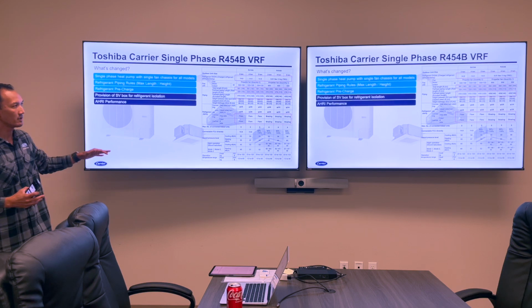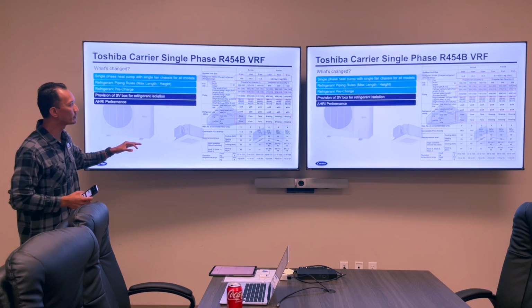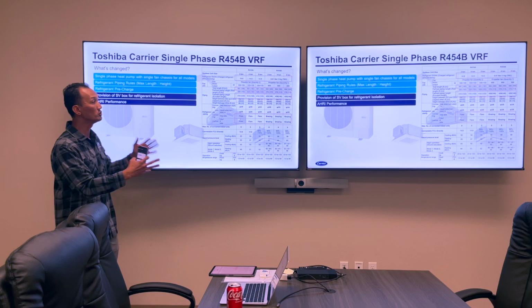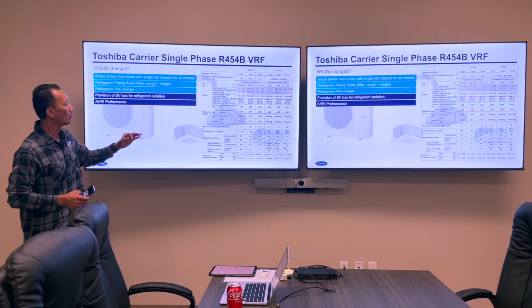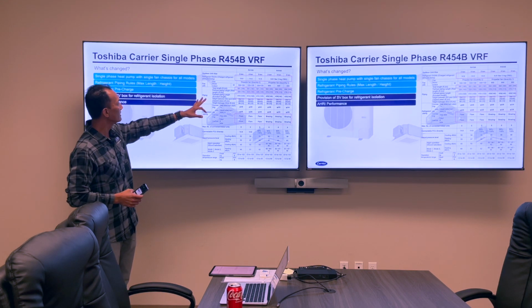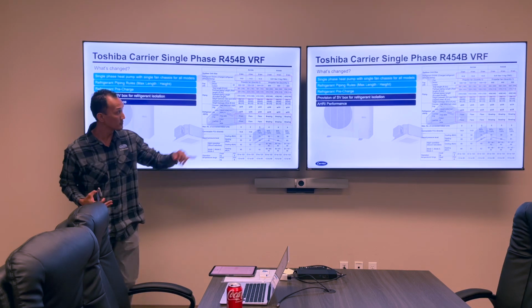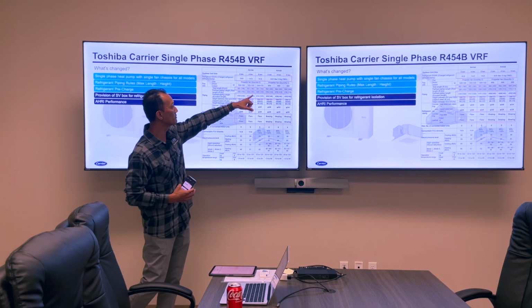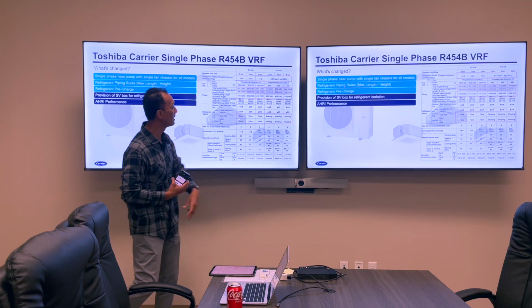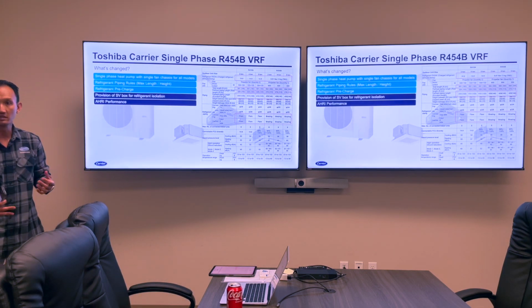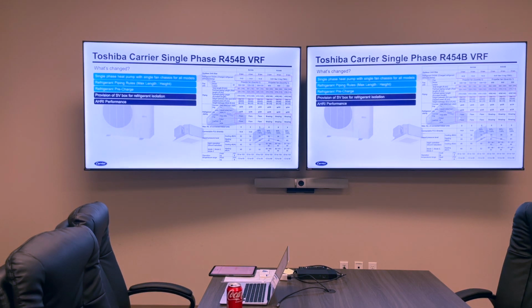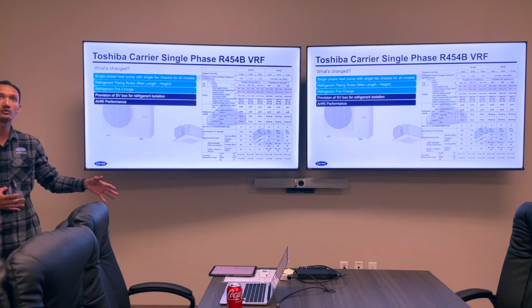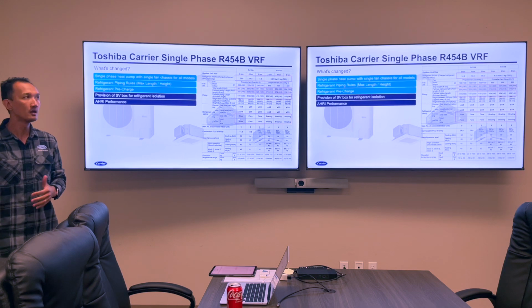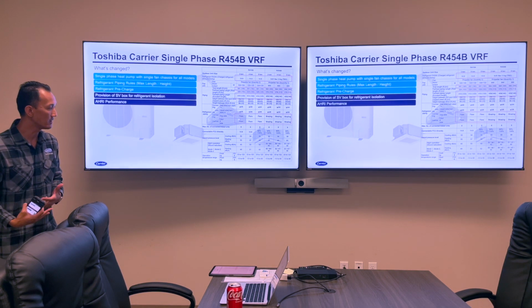For Toshiba Carrier single phase, we've made some improvements with the new version. One of the things we want to point out is piping lengths. We almost doubled the total amount of pipe that we can use, from 591 feet to 984 feet. And then the furthest piping length, from your outdoor unit to your furthest fan coil, we made some improvements there as well.